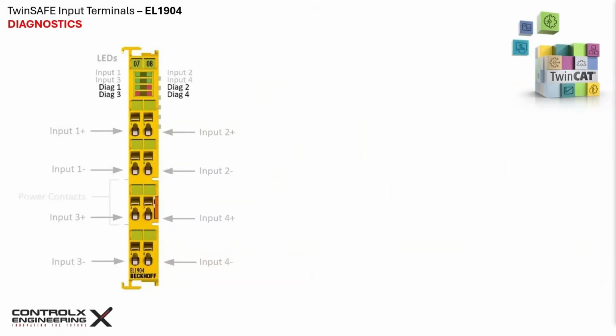This terminal also has 4 diagnostic LEDs. Diagnostic 1 green LED indicates normal operation and should always be on, which indicates that the EL1904 is functioning correctly. If this green LED is flickering rapidly, it indicates various error conditions depending on the number of flashes. Diagnostic 2 LED illuminates red if the terminal detects an external supply or a cross-circuit detection. This LED turns off once the error is rectified. Diagnostic 3 and 4 LEDs flash to indicate other types of serious error conditions like over temperature, over voltage, etc.